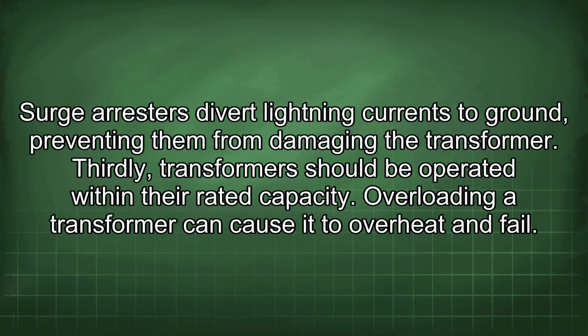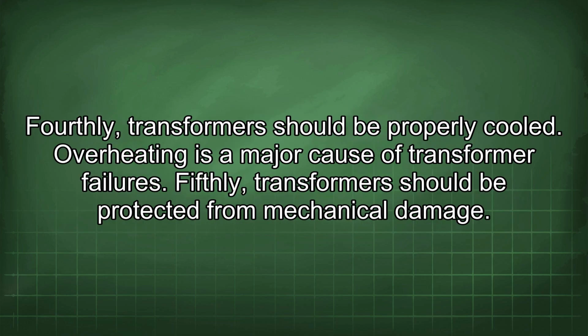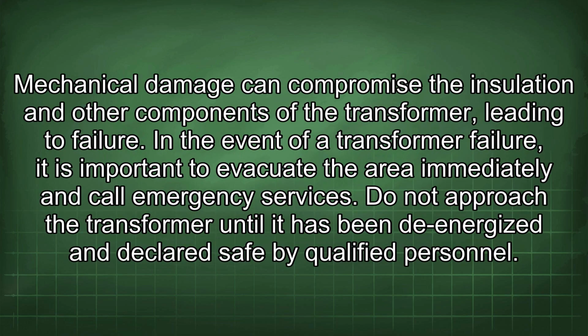Thirdly, transformers should be operated within their rated capacity. Overloading a transformer can cause it to overheat and fail. Fourthly, transformers should be properly cooled. Overheating is a major cause of transformer failures. Fifthly, transformers should be protected from mechanical damage. Mechanical damage can compromise the insulation and other components of the transformer, leading to failure.